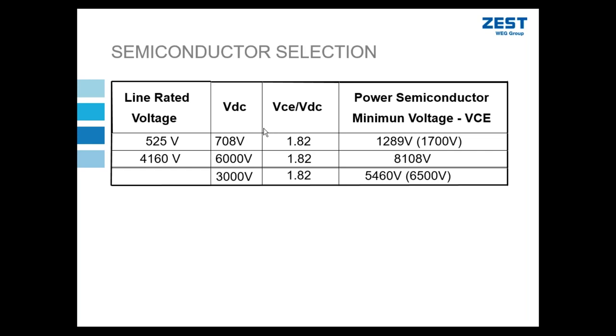But I want to design this VSD with a safety margin built into my IGBT. I don't want my IGBT failing. The general rule of thumb in power electronics is to use a safety factor of about 1.82. So if I'm switching 708 volts, I need to provide an IGBT that is at least rated for 1,289 volts. In the marketplace, it is possible to buy 1,700 volt rated IGBTs, and so those are the IGBTs of choice for 500 volt VSDs.